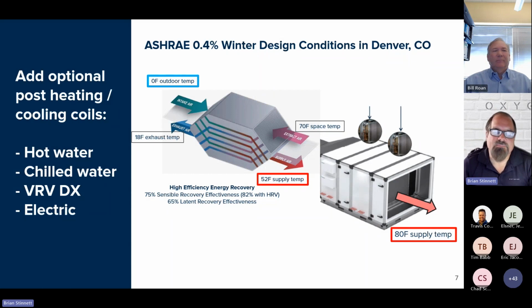It's much simpler then to heat that 52 degree air up to whatever temp you might want to deliver to the space. Do you want to supply 60 degrees? Do you want to supply 70 degrees? Do you want to supply 80 degrees? Now we can use an electric coil, a VRV DX coil, a hot water coil, a number of different options to do that final trim heating to bring that ventilation supply air up to the temperature that we want.